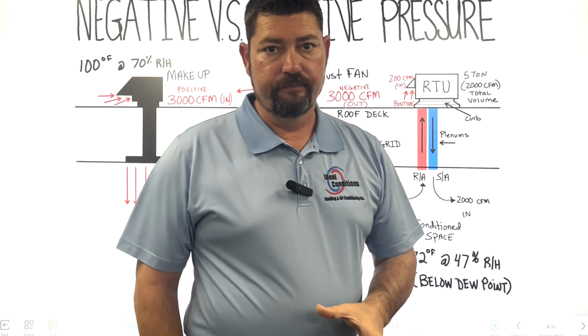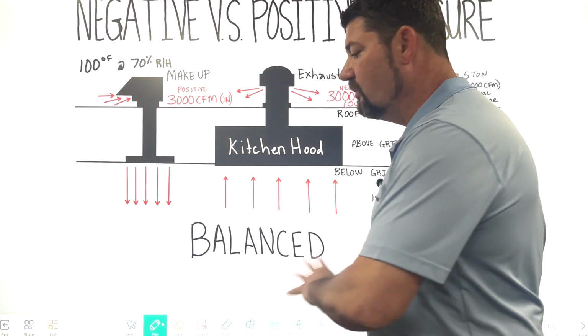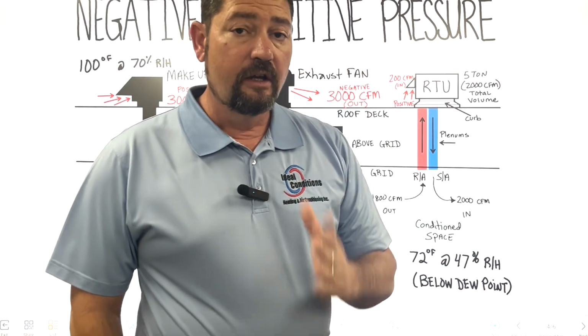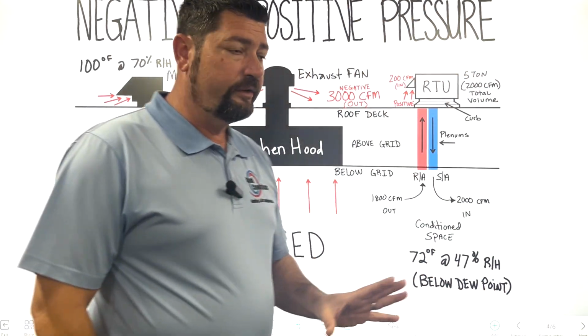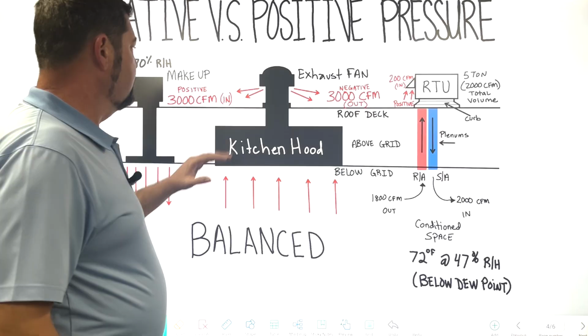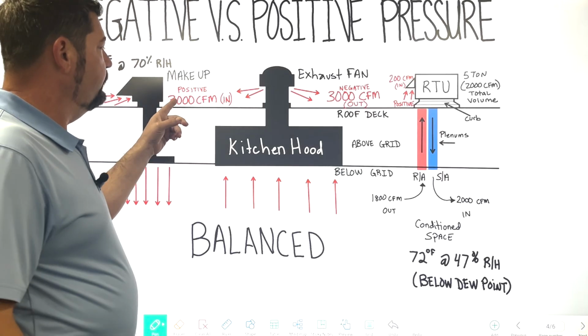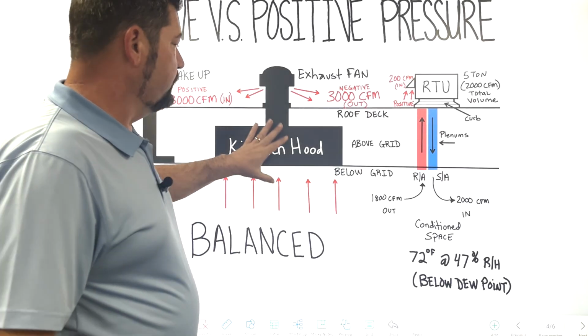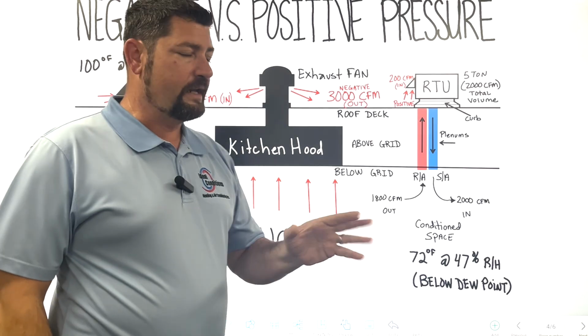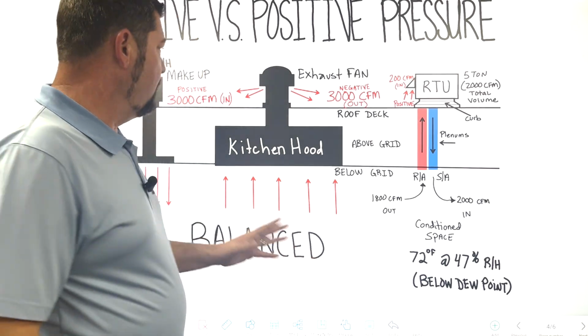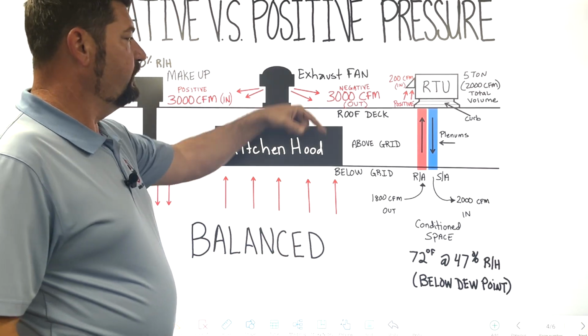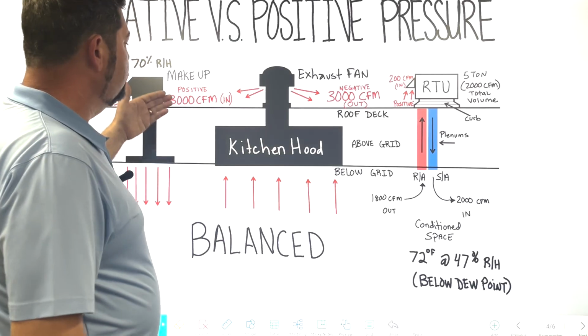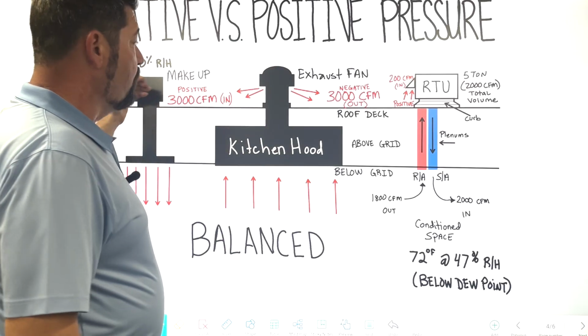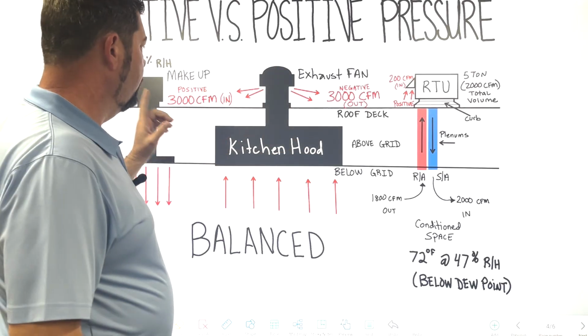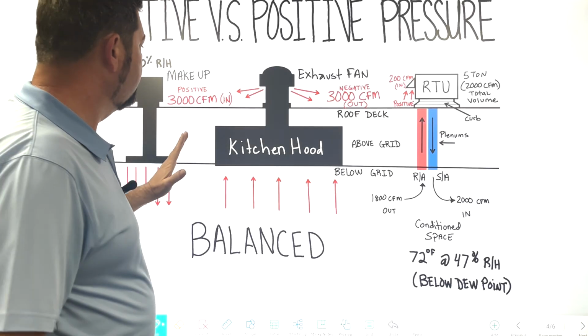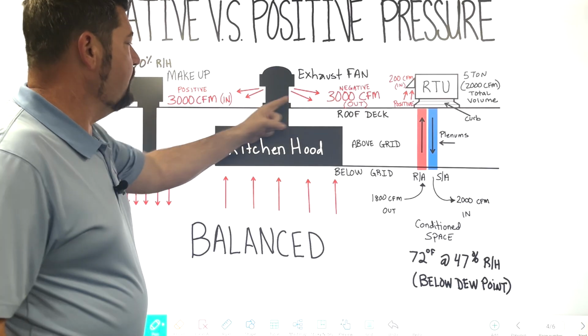Here's the issue, okay? There's everything there. Rewind it 100 times, 1,000 times. Learn it. This is as simple as it gets. Don't take these numbers like you have to have 3,000 CFMs coming into a building and your kitchen hood taking 3,000 CFMs out. That's not the point, because maybe this is 750 in, 750 out. Maybe it's a small hood. Maybe it's 2,000 and 2,000. Maybe it's more than that. It doesn't matter. What matters and what you need to take away from this is these numbers are the same.